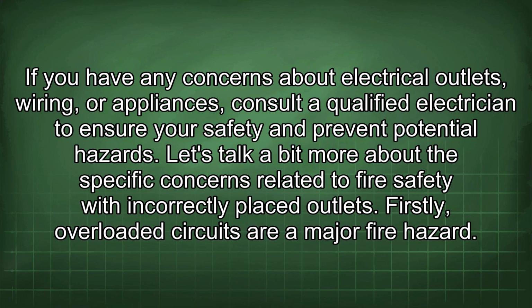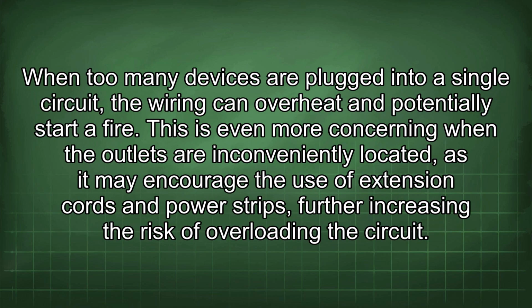Let's talk a bit more about the specific concerns related to fire safety with incorrectly placed outlets. Firstly, overloaded circuits are a major fire hazard. When too many devices are plugged into a single circuit, the wiring can overheat and potentially start a fire. This is even more concerning when the outlets are inconveniently located, as it may encourage the use of extension cords and power strips, further increasing the risk of overloading the circuit.